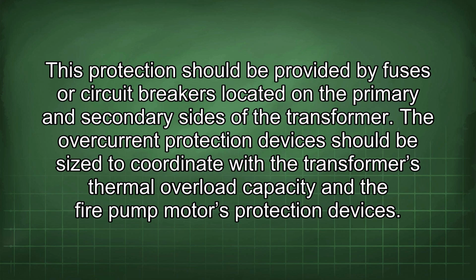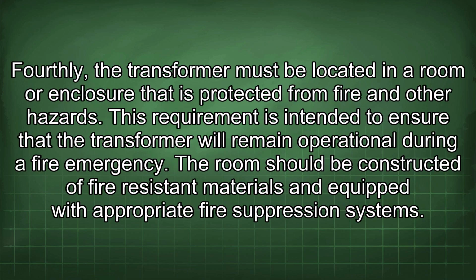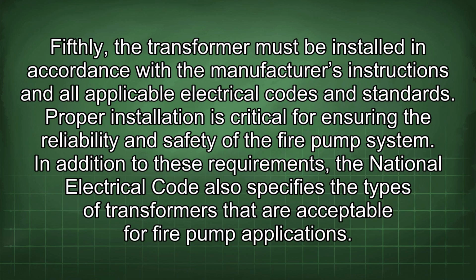Fourthly, the transformer must be located in a room or enclosure that is protected from fire and other hazards. This requirement is intended to ensure that the transformer will remain operational during a fire emergency. The room should be constructed of fire-resistant materials and equipped with appropriate fire suppression systems. Fifthly, the transformer must be installed in accordance with the manufacturer's instructions and all applicable electrical codes and standards. Proper installation is critical for ensuring the reliability and safety of the fire pump system.